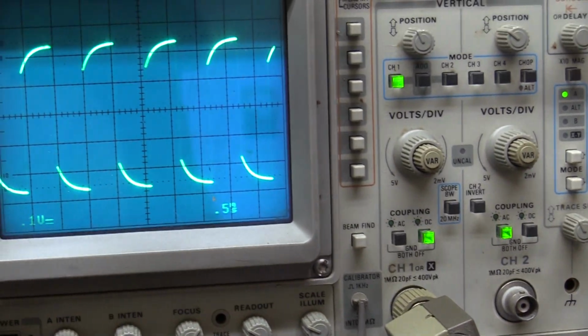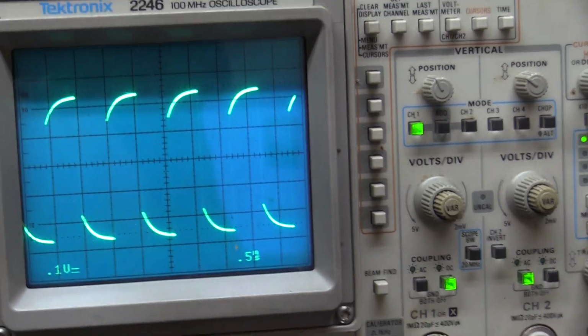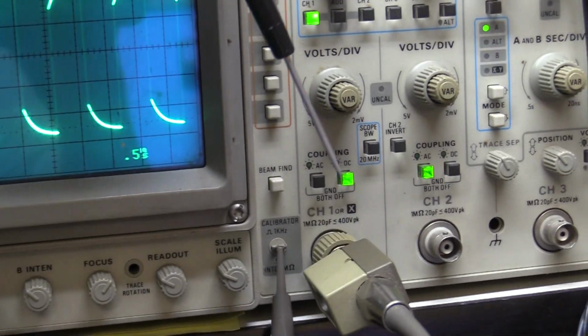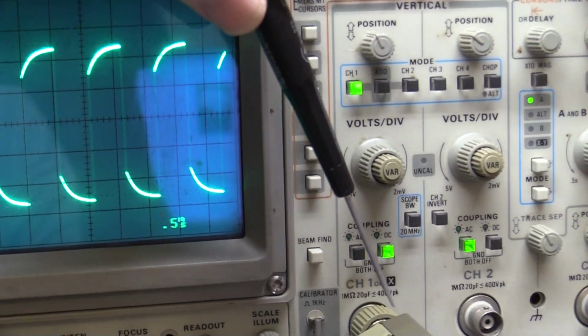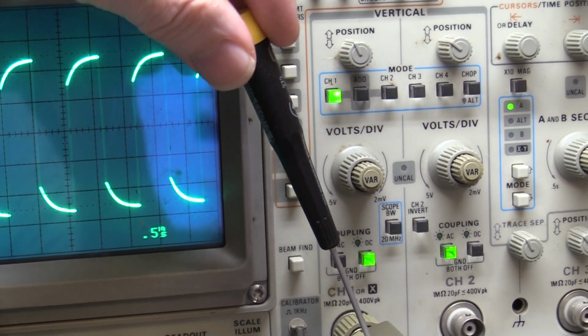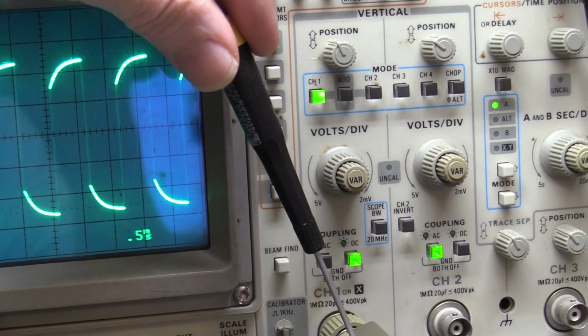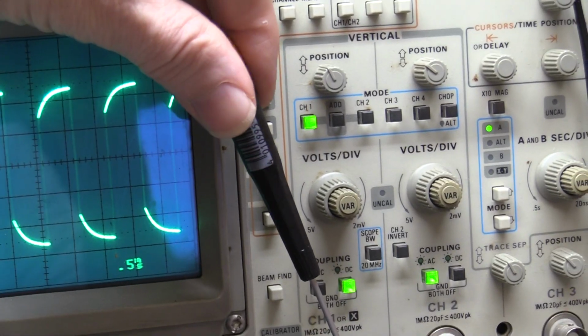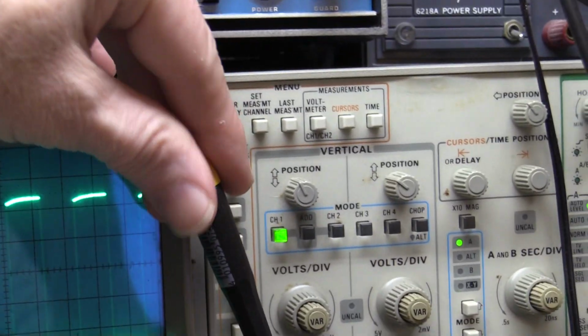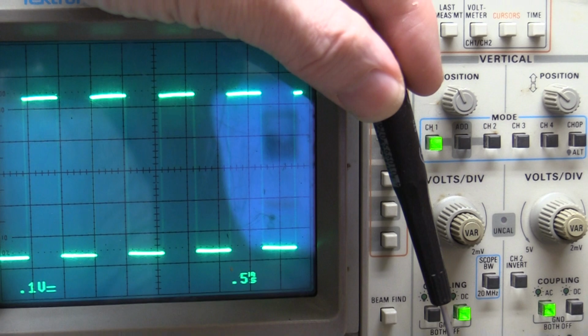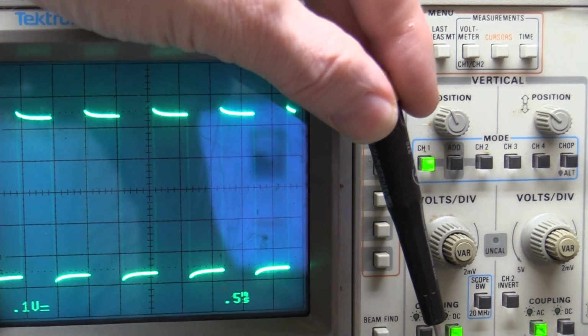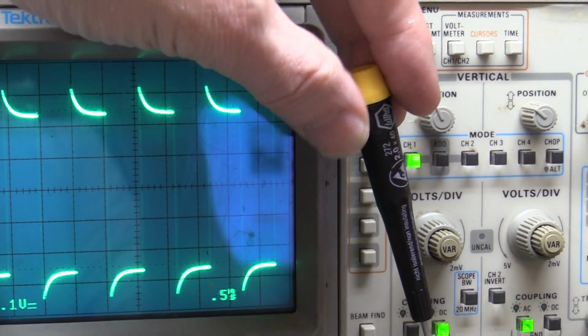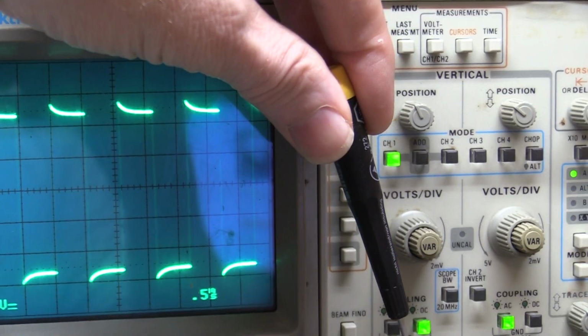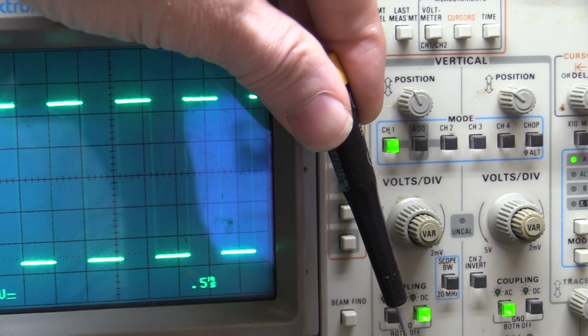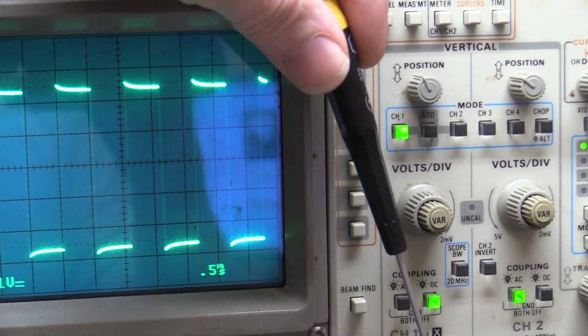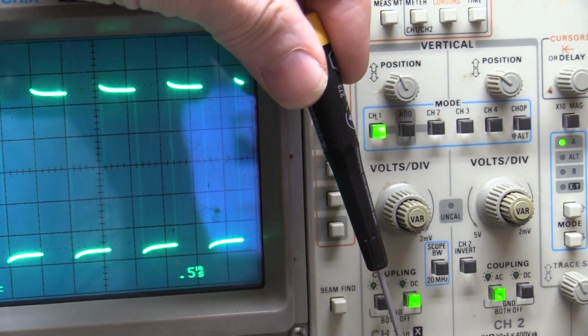The way that the adjustment is made is you hook it up to a square wave, and right now, as I said, it's very undercompensated, so we have this very rounded square wave, and by adjusting the probe we can change it to be properly compensated or overcompensated. So this will be a setting that might need to be made depending on the oscilloscope that it's hooked up to, because it relates to the input impedance.